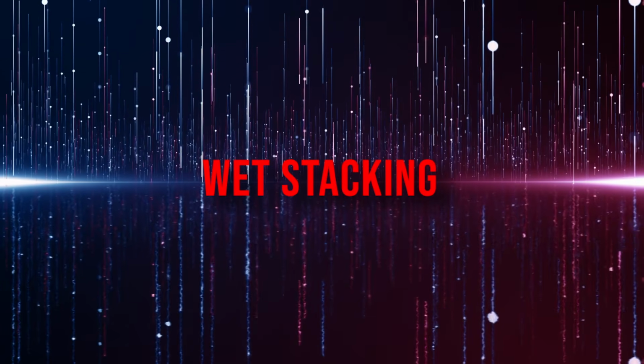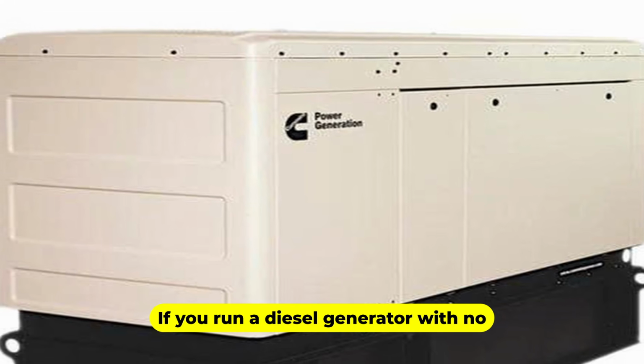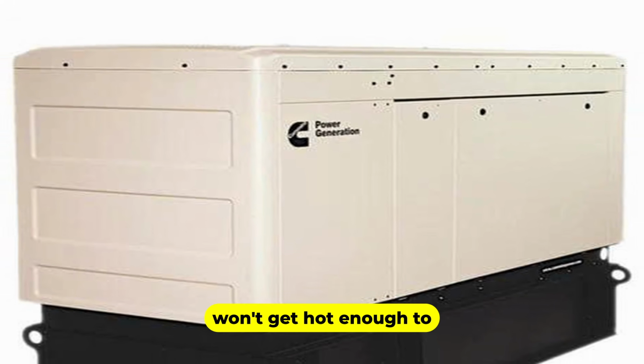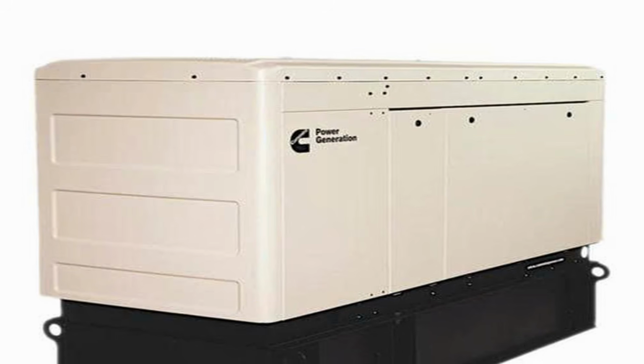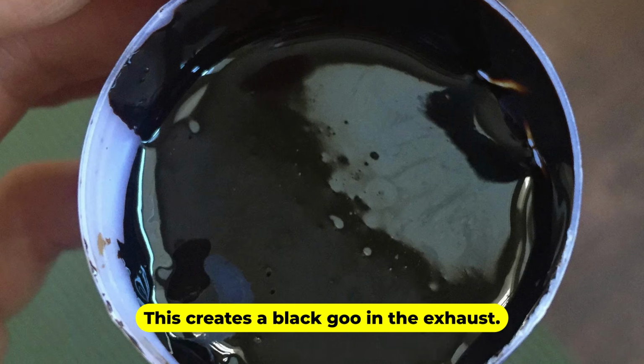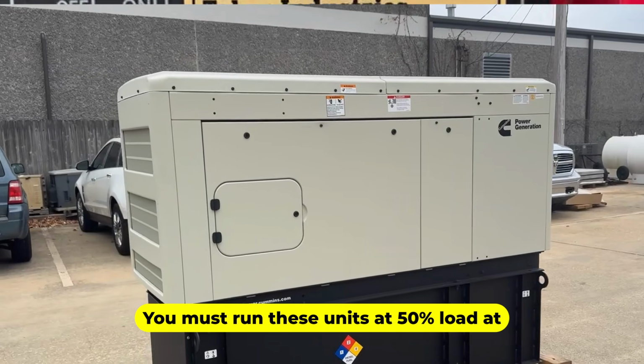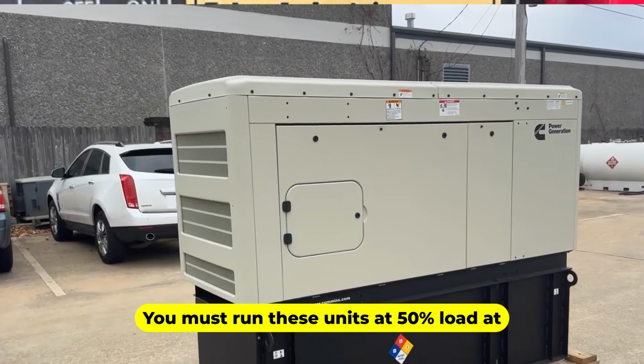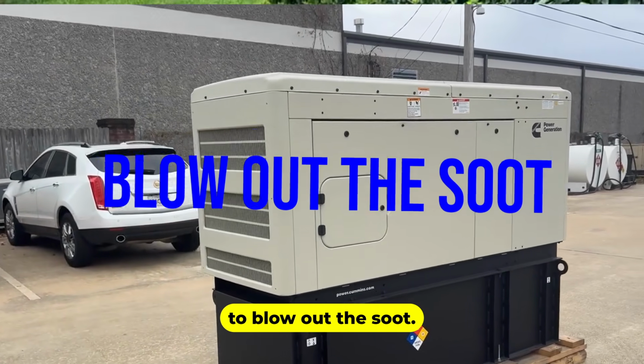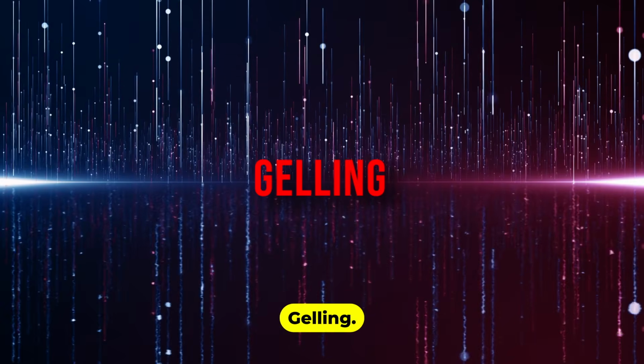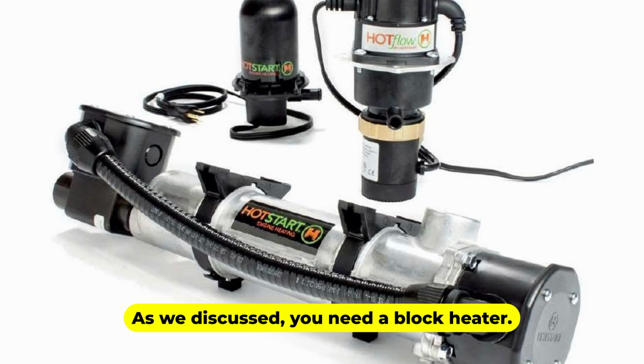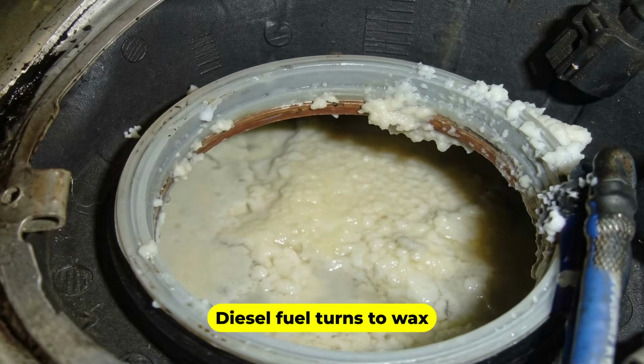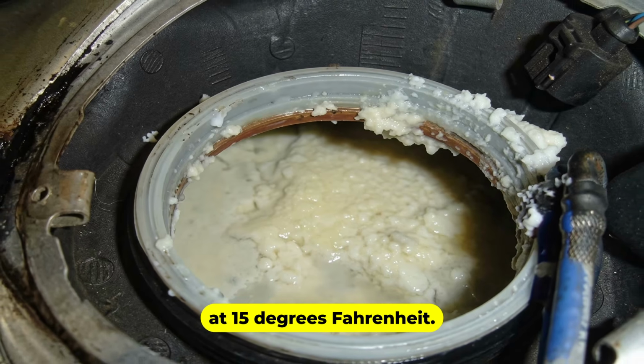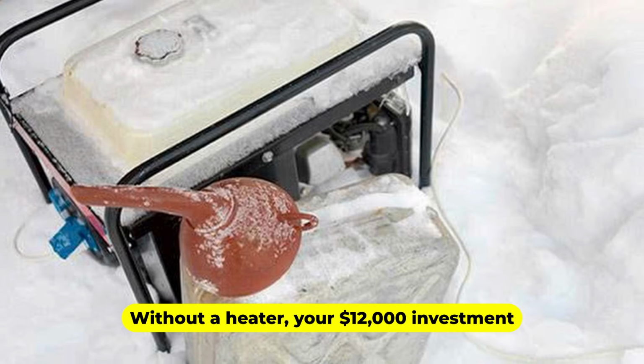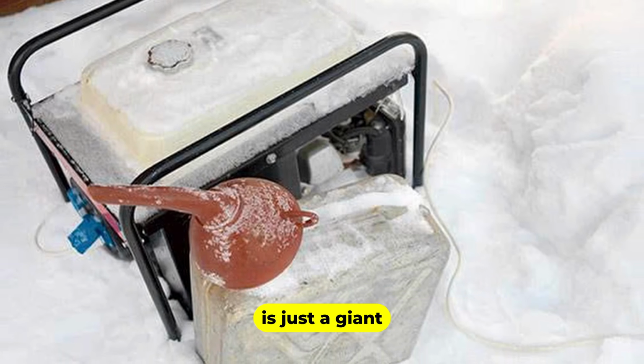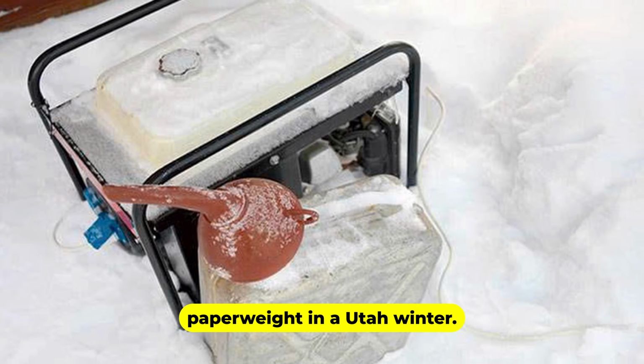Wet stacking. If you run a diesel generator with no load for too long, it won't get hot enough to burn all the fuel. This creates a black goo in the exhaust. You must run these units at 50% load at least once a quarter to blow out the soot. Gelling. As we discussed, you need a block heater. Diesel fuel turns to wax at 15 degrees Fahrenheit. Without a heater, your $12,000 investment is just a giant paperweight in a Utah winter.